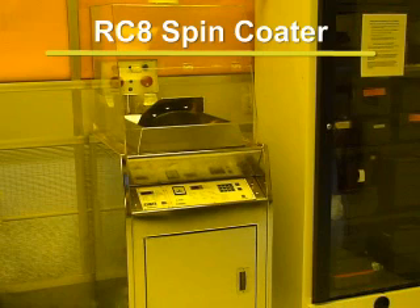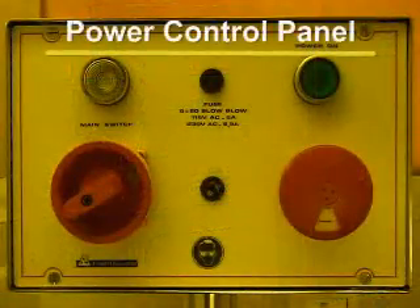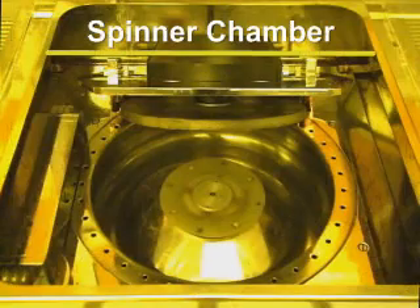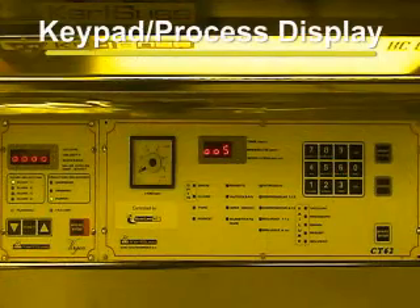The Karl Suss RC8 spin coater is used to evenly distribute photoresist across the surface of photosensitive substrates. There are three main parts to the system. The power control panel is where the power on and emergency shutoff buttons are located. The spinner chamber is where the spin chuck is located and where the coating takes place. The keypad and process display panel is where the parameters of a process can be entered and adjusted.